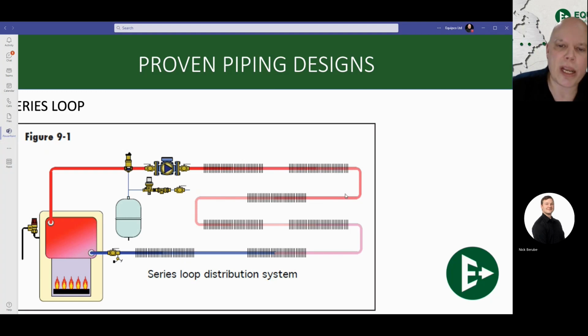So that means that as a designer, we have to design each radiator to give off the right amount of heat at a cooler water temperature. Now there are all sorts of formulas that we can use to see how much temperature drop we're going to have from one rad to the next rad, but just know that this is going to be a symptom of using a series type design, where you need to oversize your last emitter and usually undersize your first emitter, because your heat's going to get lower and lower as you go forward.